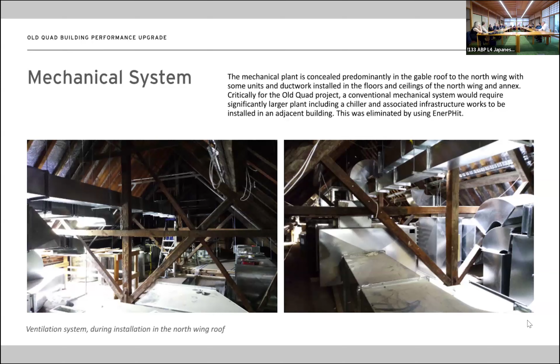As you see, we were pretty short and tight on space. We had to work within the space that we have available. We actually used plate heat exchangers. They're 75% efficient. If we had more space and more room to deal with, we might have put in thermal wheel rotary heat exchangers, which give us an extra 10%, or what you commonly see in whole house ventilation is regenerative heat exchangers. Now, those passing the airstream over the same surface, they can be about 95% efficient. So what that means is 95% of that heat that's going out of your house or your space is reclaimed, coming back in. So that's the most efficient that you can possibly have. But obviously, working within an existing building, we are more constrained. Go to the next slide.